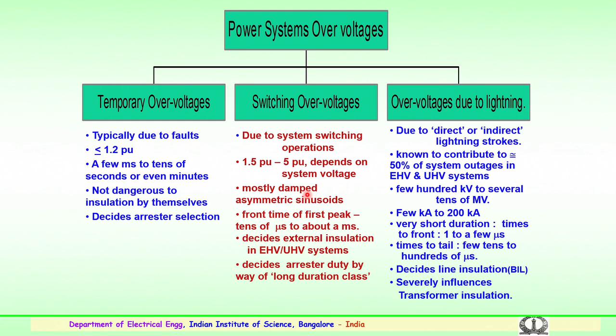So this could be for a very short duration, and the voltage levels could be a few hundred kilovolts to several tens of megavolts. These are the observed lightning overvoltages in the field, and the currents during a lightning strike could range anywhere between a few kiloamperes to 200 kiloamperes. Here again the line insulation, or the basic line insulation, has to be looked into for the performance of the equipment system in case lightning strikes the equipment. It severely influences the transformer insulation. Lightning, or very sharp pulses, could affect the transformer insulation, so proper protection has to be done.